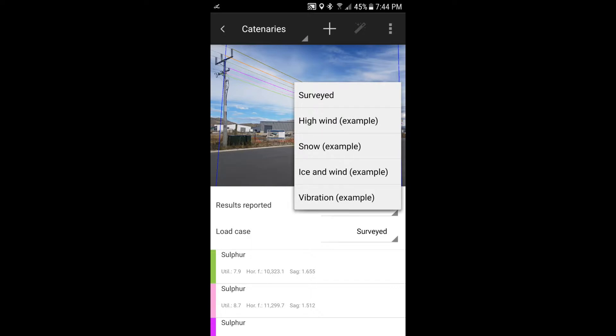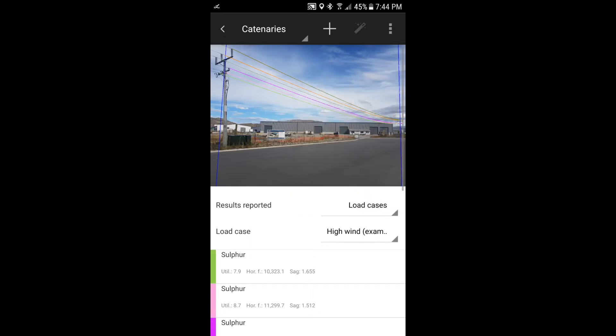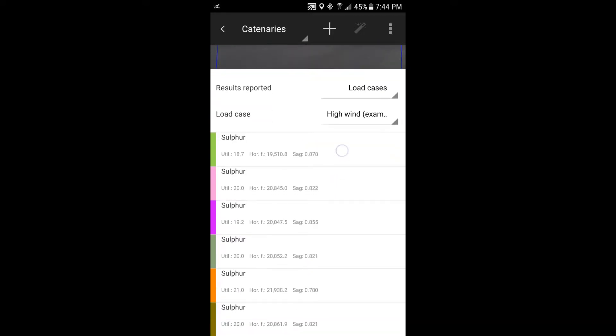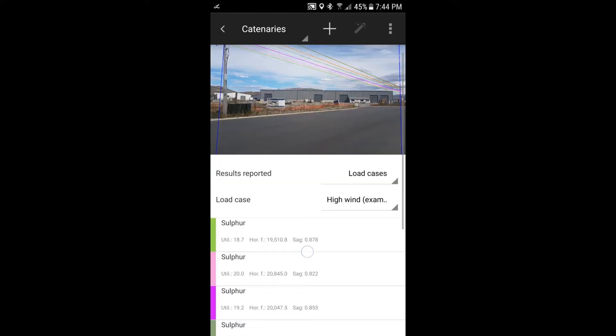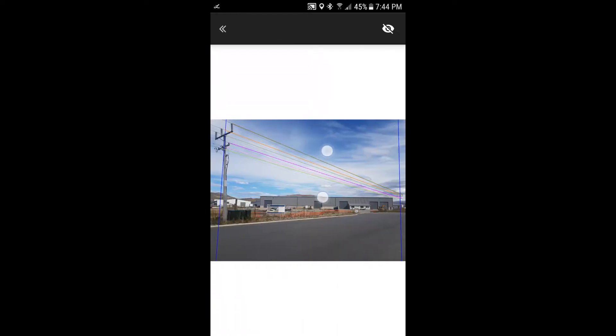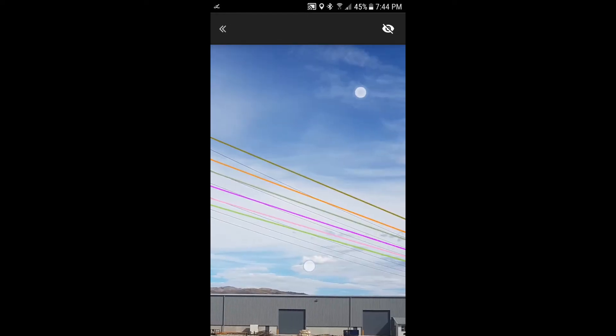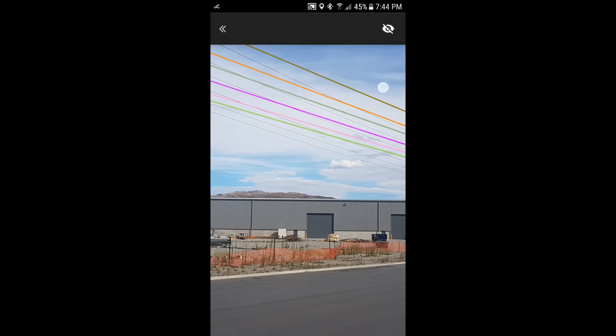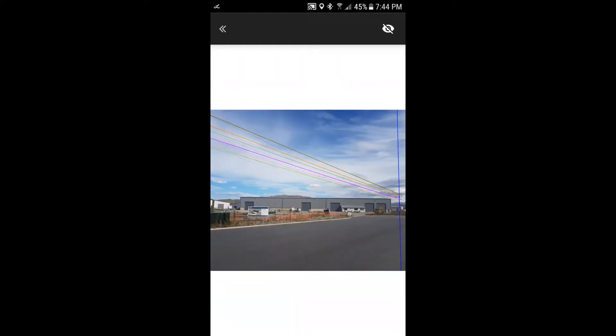So we could, for example, look at high wind, if we select that, and the tensions change. They go up because you've got more load on the conductors and the sags change and so forth. And so the same thing can be done for your ground clearances and what have you. And if we look on the image here, you can see that the conductors have been blown out to the side of where the conductors actually were when they were surveyed.